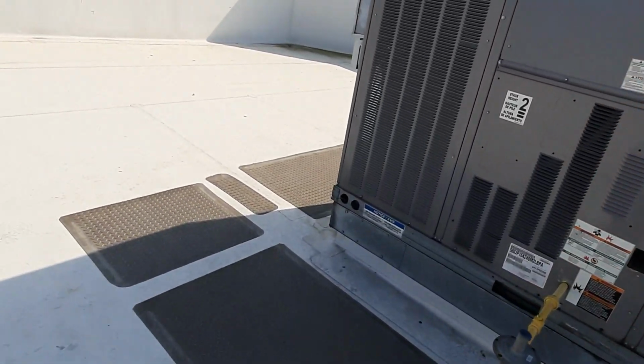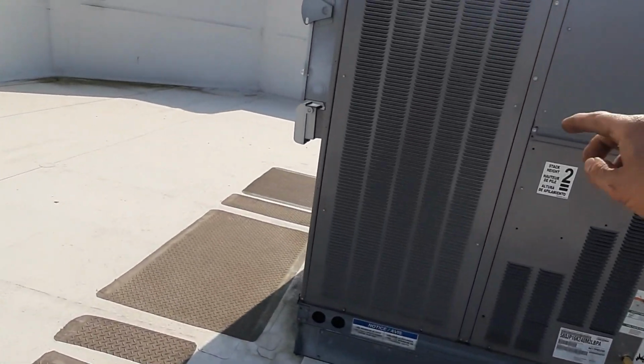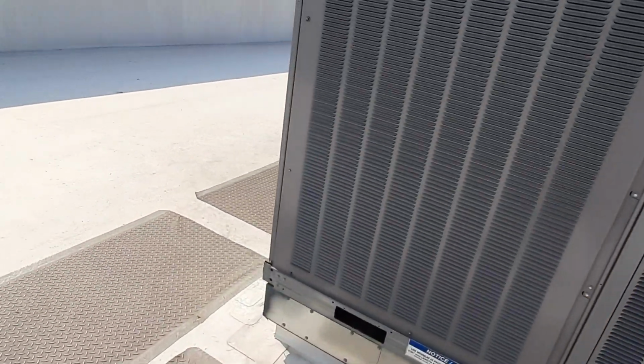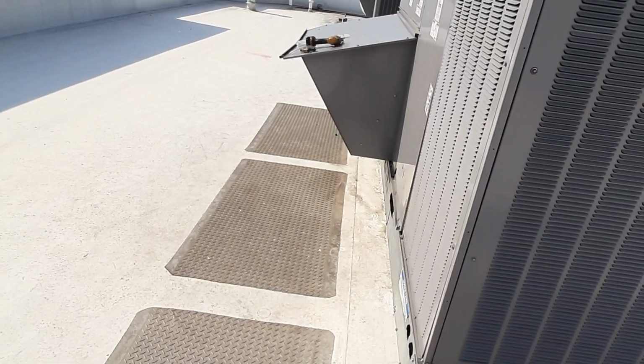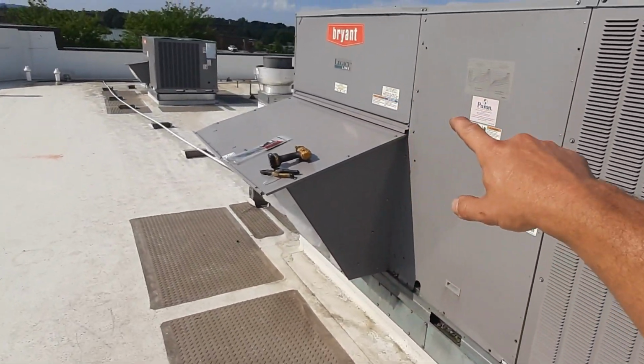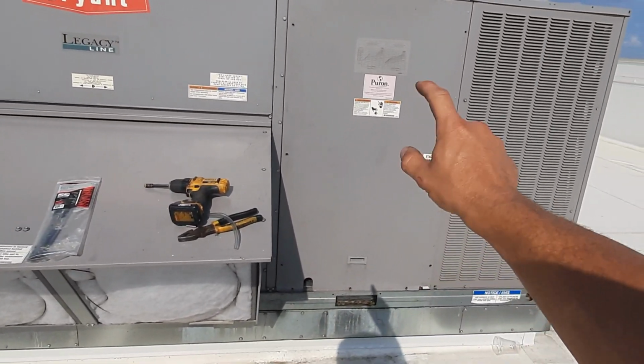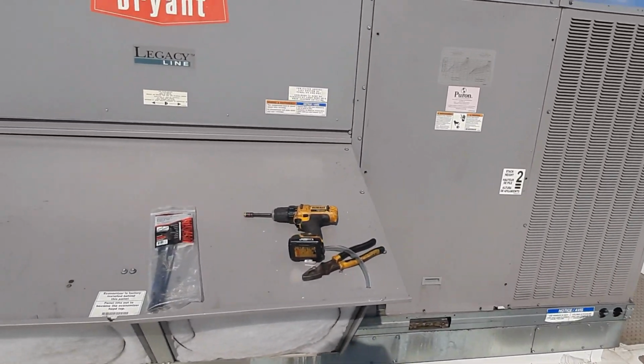I do have to come back and put a pound. That's probably going to be a real quick dump a pound and let it go, because all of my readings so far have been amazing. So we got both of these guys working great, and we'll come back, check on the temperature, put a pound, 12 ounces into stage 1. We ought to be good from there.